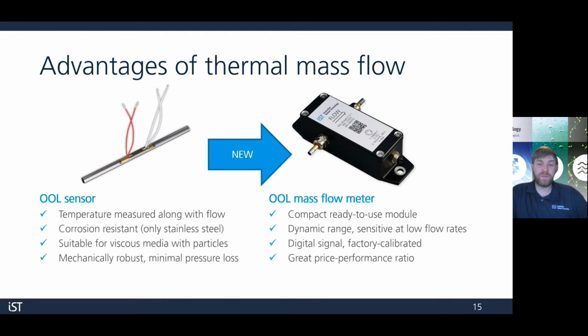This setup gives us the ability to measure both flow and temperature because of the onboard RTD. It's corrosion resistant since only the stainless steel is in contact with the liquid. And it's also suitable for different flow types, including viscous media or media with particles. Additionally, with this robust setup, we have minimal pressure loss.